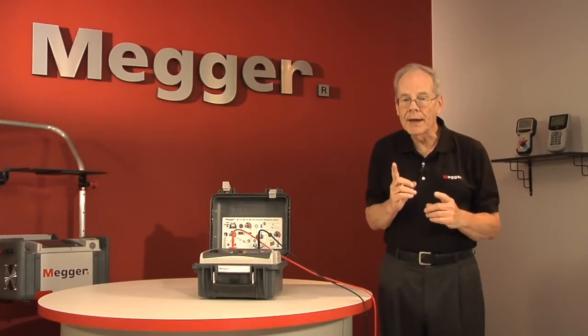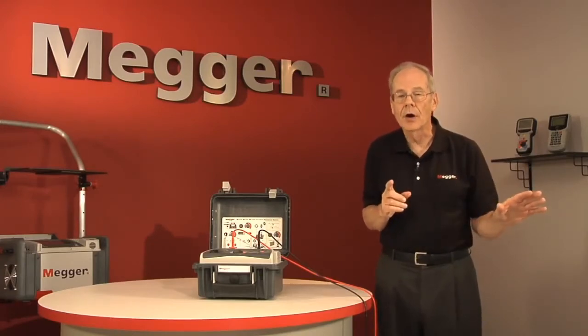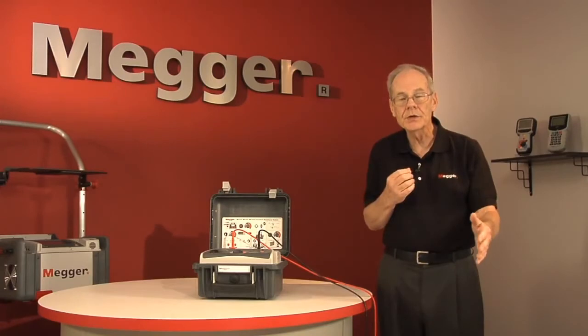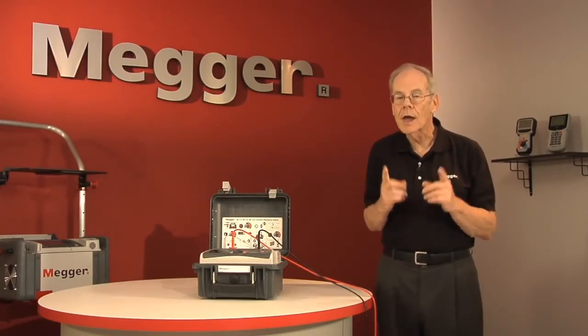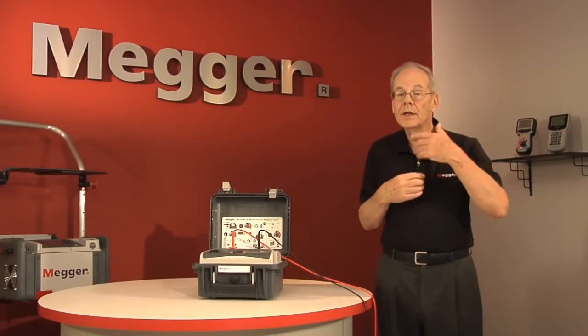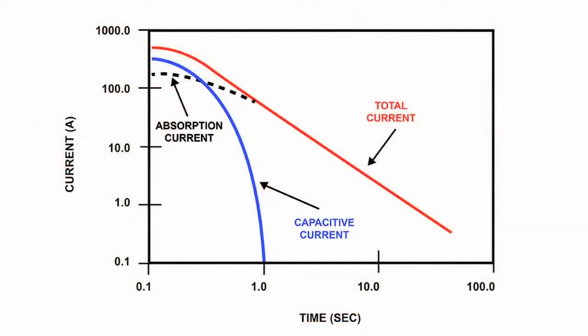The tester waits a minute so that the capacitive current, which is of no concern, has been discharged, and then it looks and measures how much leakage current, what we call absorption current actually, is still flowing. And this is the current that's been stored in the insulating material. And at the end of the test, it calculates again a figure of merit like you get with the polarization index test, except the numbers are the reverse. Now you want low numbers. A good number is 1. And the higher, the worse it is.